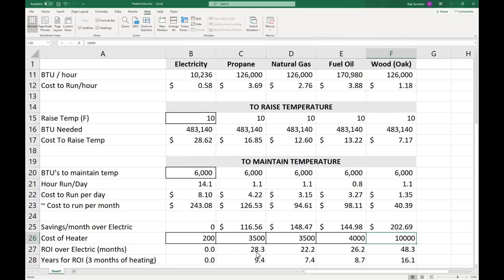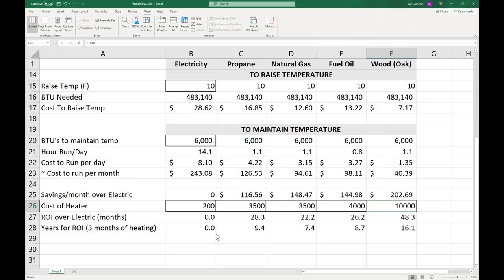Based off of that savings, we can figure out what the return on investment is compared to heating with electricity. For example, if I installed a propane heater, it's 28 heating months of time to pay for that heater. So really, if I was heating just for 3 months, it's 9 years for that propane heater to pay for itself versus that little tiny electric heater. And 16 years for an outdoor wood boiler. Again, these are much larger heating systems, so you're probably using them for other parts of heating. But I wouldn't say it's a perfectly fair comparison. By changing these numbers up above, by getting a fairer heater in there, it might be a little bit better. But overall, 7 to 10 years for conventional heating. By that time you've probably worn it out and have to replace it. The boiler tanks you might get 10 years out of it. So to put an outdoor wood boiler in just for heating water probably isn't worth it, plus all the time it takes to cut the wood and get that ready. So a little bit interesting on the year return on investment.